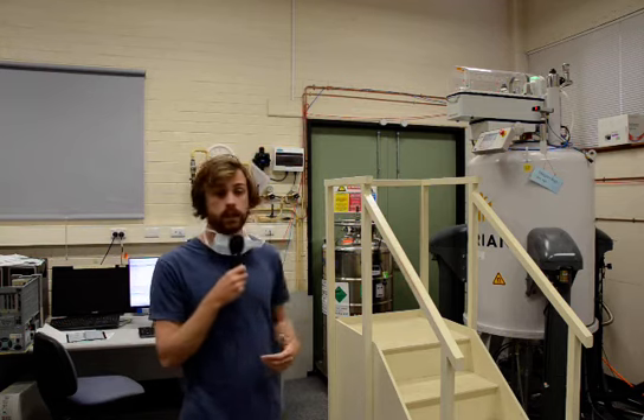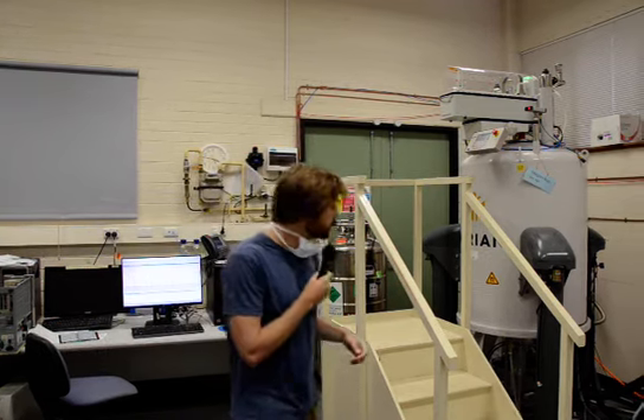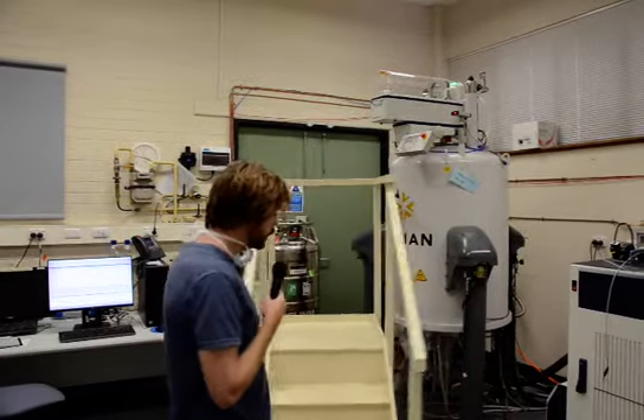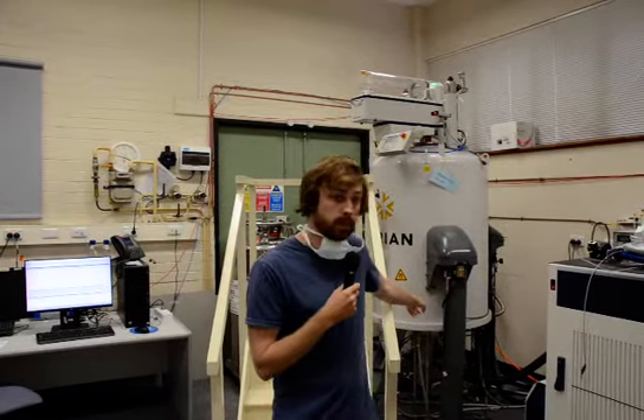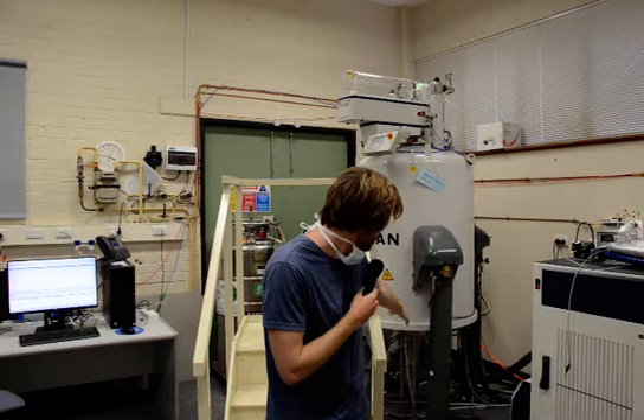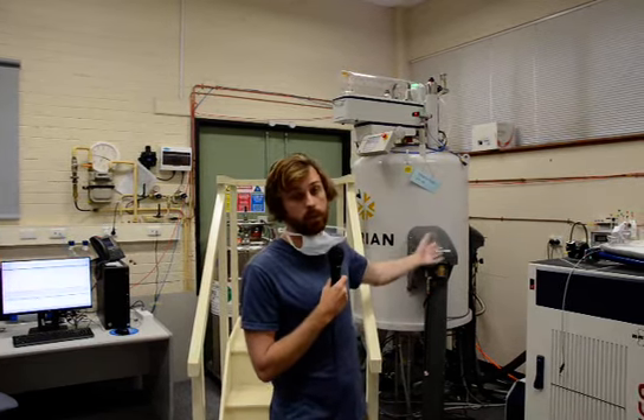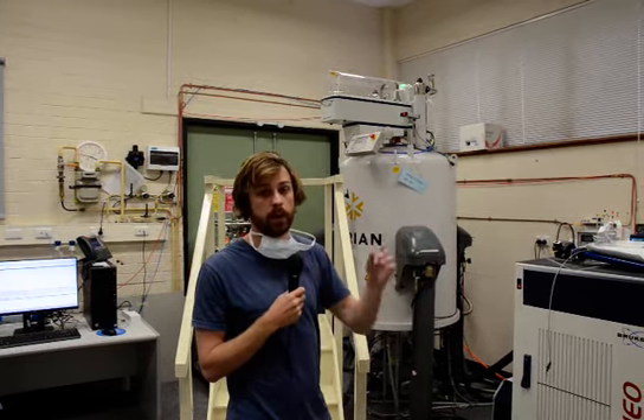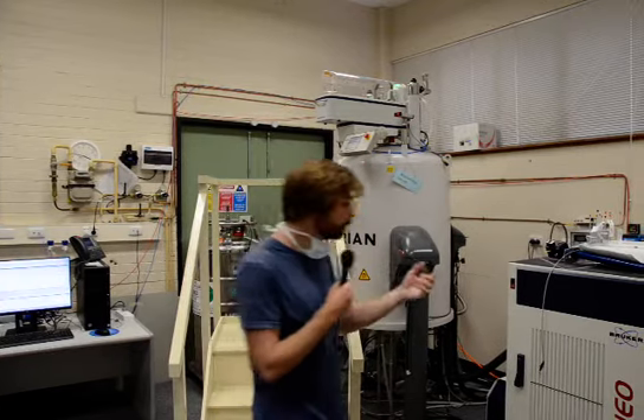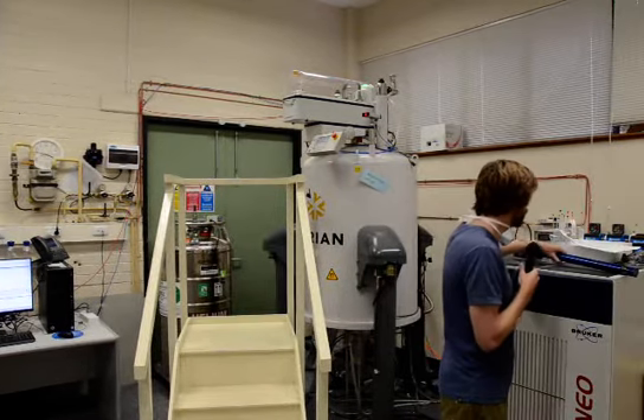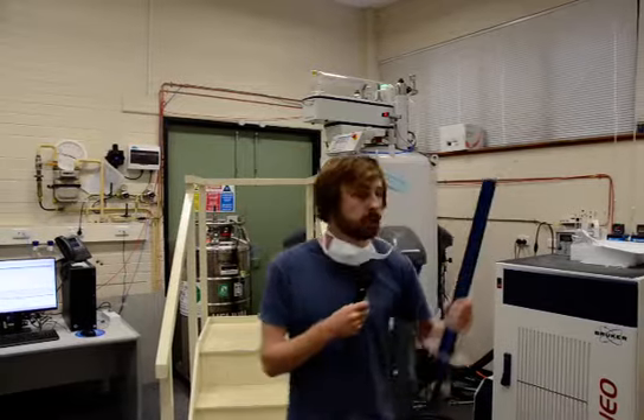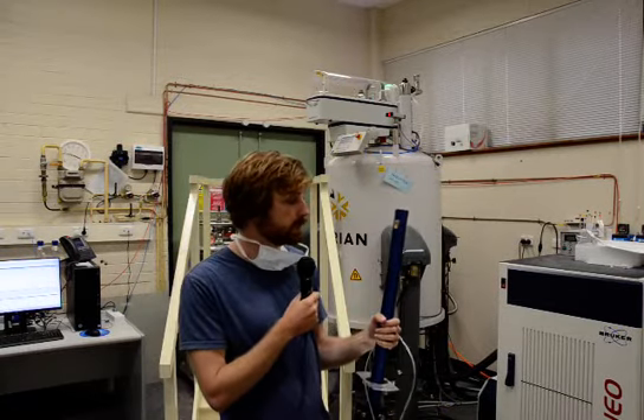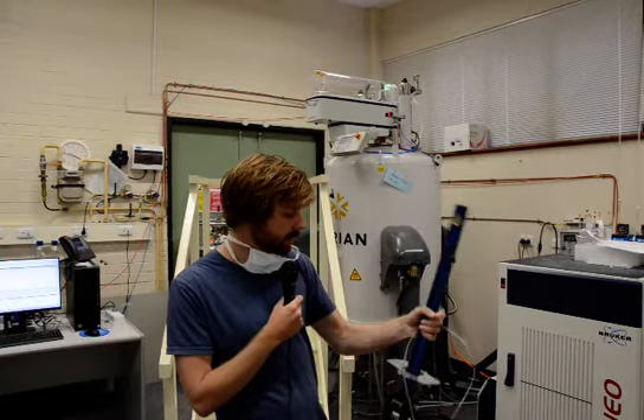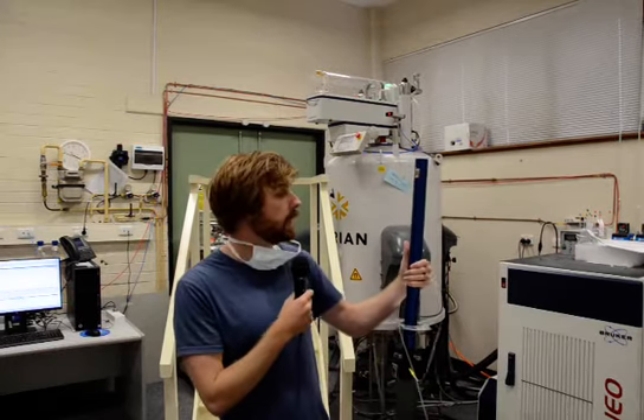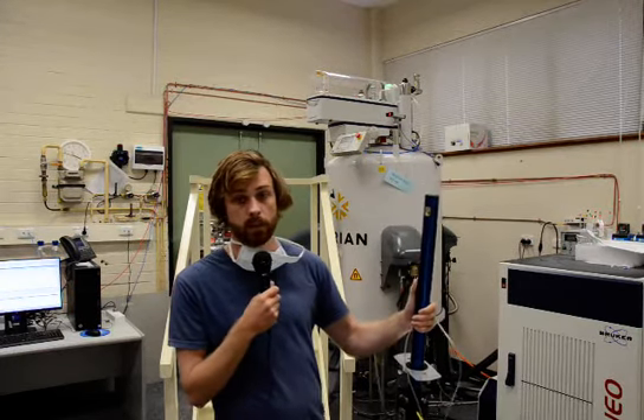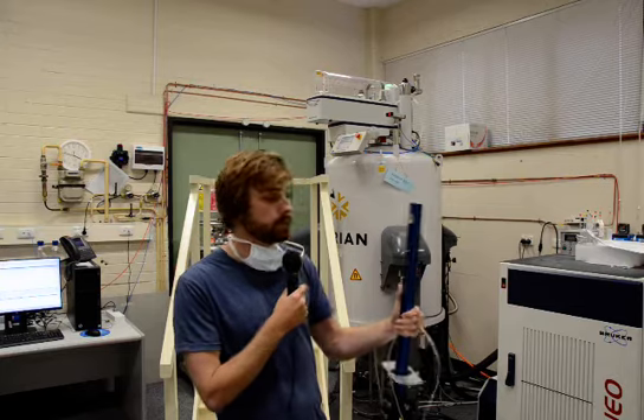So what we're going to do now is we're actually just going to take a look at the probe in the machine. So what happens here is the probe is in the center of the machine, in between the magnet. So you can see at the bottom, at the center, straight up through the middle of the spectrometer would be the sample probe, where the sample is spinning. So we've actually taken one out of a spectrometer here. This is a magic angle spinning probe. And what happens here is you actually have this inside the instrument, and it sits in the middle of the magnet where it's going to acquire the best data, and the sample will spin around.